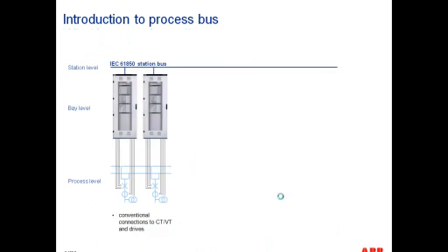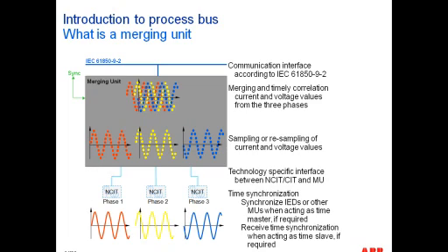So, what is a merging unit? Well, just so that we define it a little bit more, in this picture we have phase A, phase B, and phase C. And what your merging unit is going to have is somewhat similar to what a relay does today. There's going to be wiring from your current and voltage transformers onto the merging unit. The merging unit is expected to be very, very close to the process, whether it's inside the circuit breaker cubicle or somewhere adjacent, so that the wiring is minimized.